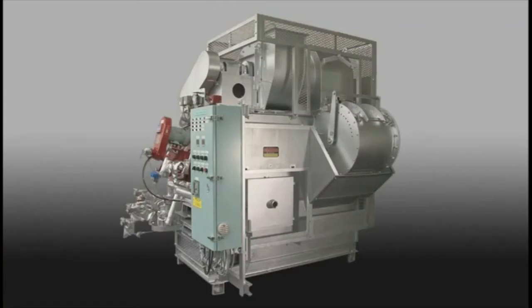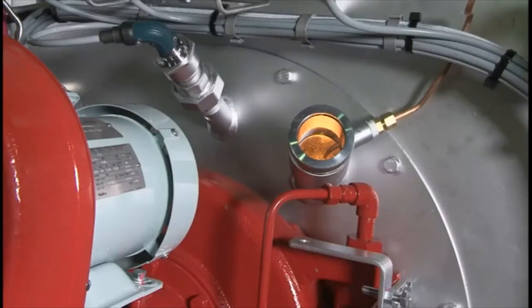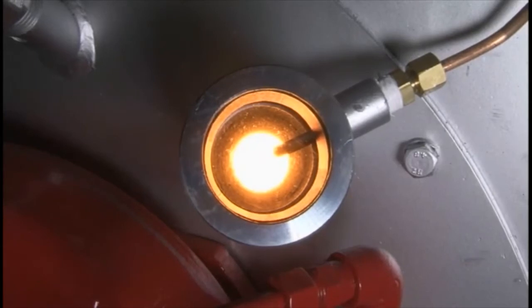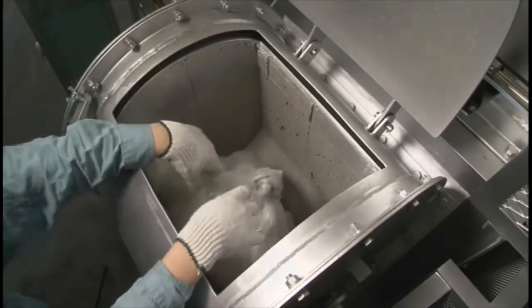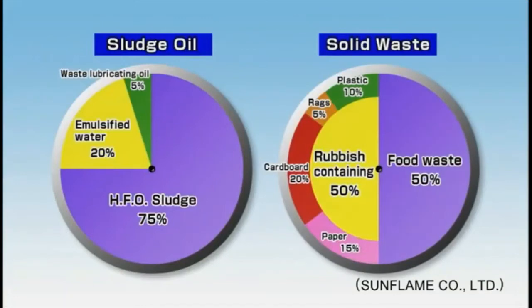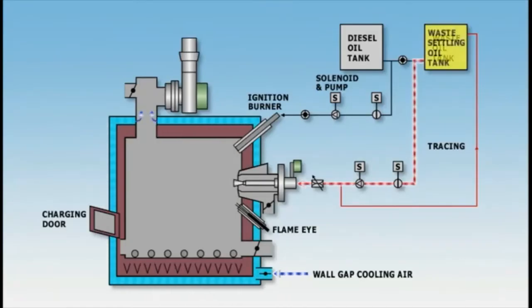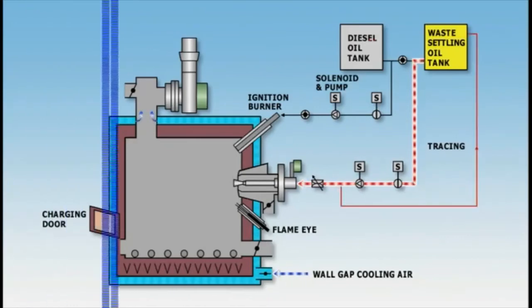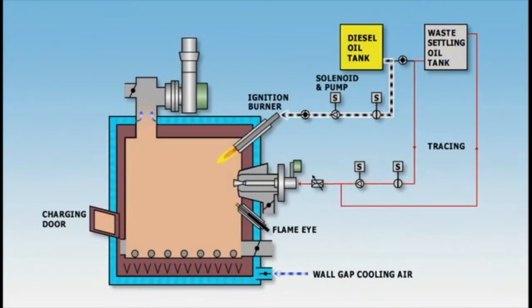The incinerator is used to incinerate waste oil from fuel oils used by the main and auxiliary engines, sludge oil from bilge separators and the like, and household and other solid wastes. After its water content has been evaporated in the waste oil settling tank, the heated waste oil is transferred by a pump via flow regulator and is then ejected from the incinerator burner. A special line returns some of the waste oil via the flow regulator to the waste oil tank. Marine diesel oil (MDO) is used for the ignition burner.